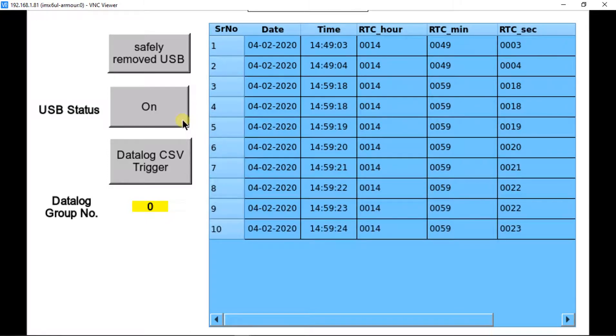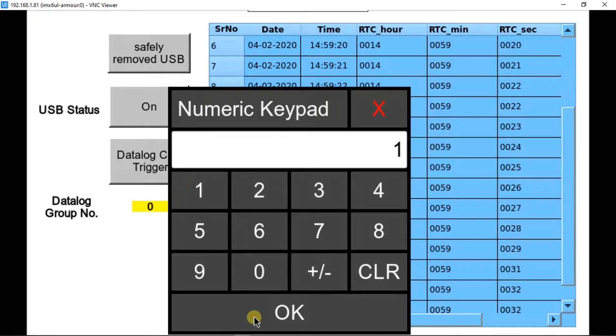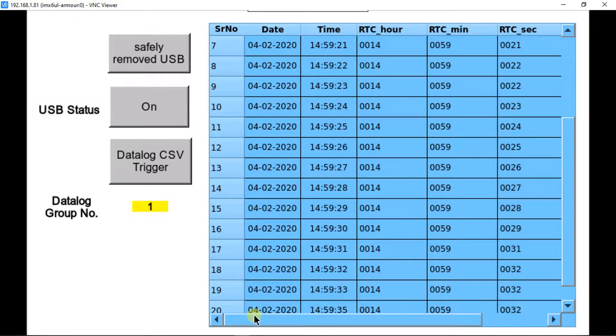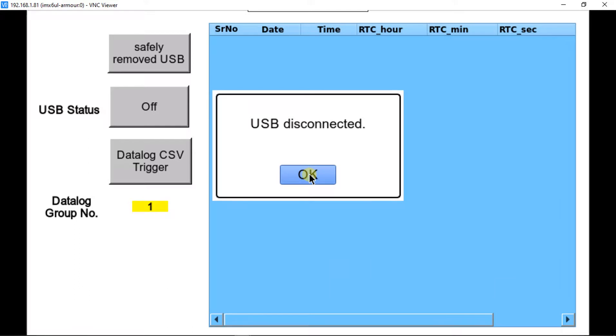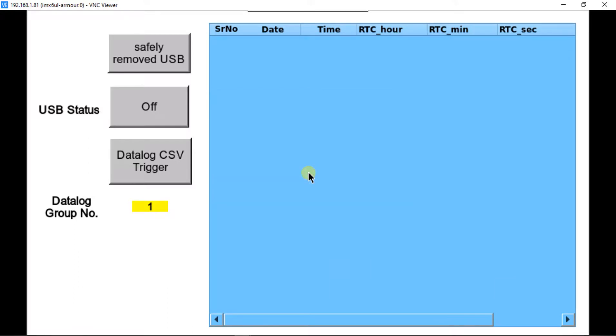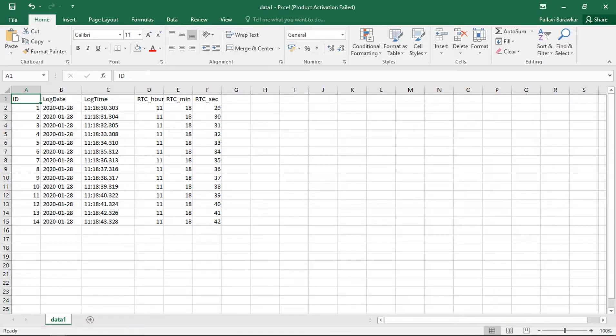USB status is also changed. Write down the data logging group number here — by default this group number is 0, which means it will log the data of all the predefined groups. It is must to click on the data log CSV trigger bit. Before removing the USB, it is must to click on 'Safely Remove USB' and wait till it shows the USB disconnected message. Now we can check the logged data from the USB stick — this is the data logged Excel file in the USB stick.